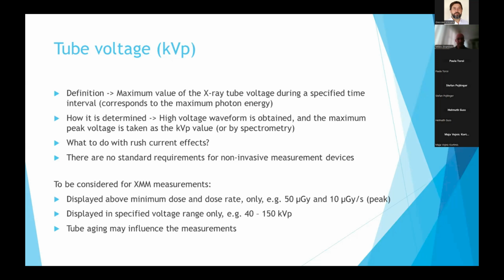And the ambiguity can be related to rush current effects, because for some X-ray machines, you can have a first peak that is much larger than the following peaks. And now it depends whether you are interested in this peak and how representative it is of the overall radiation quality and of the dose that the patient will receive. So if you want to exclude it, then of course you will get a different value than if you also include the first peak. There is another problem: there is no IEC standard for devices that measure kVp. So then, of course, there are also no limits of variations and other data that we would get from a standard.